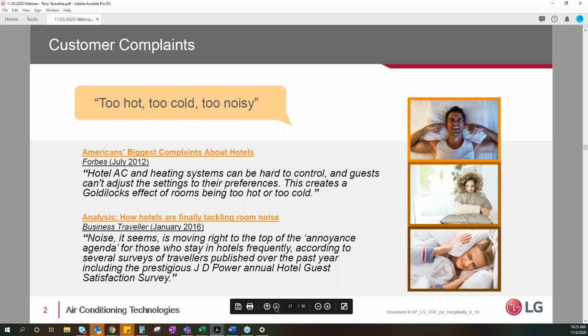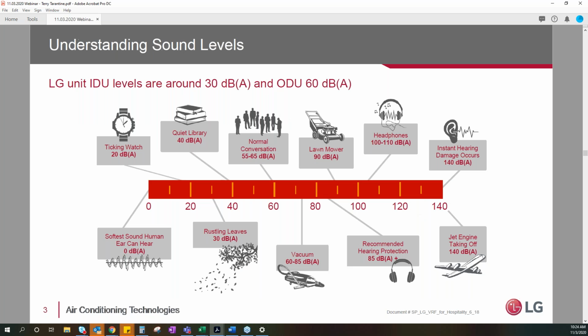Water source heat pumps are typically near the space, and the compressor is mounted inside that particular unit. So you have multiple compressors throughout the building, and they can lead to some noise issues, whereas VRF is incredibly quiet. Very often the occupants don't even know the system is running, it's that quiet. So that is an issue for a lot of hotels. And then efficiency. Between water source heat pump and VRF, it's a direct net savings to go to that higher efficiency system.